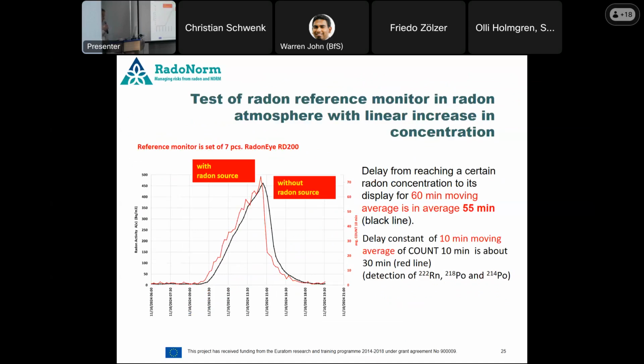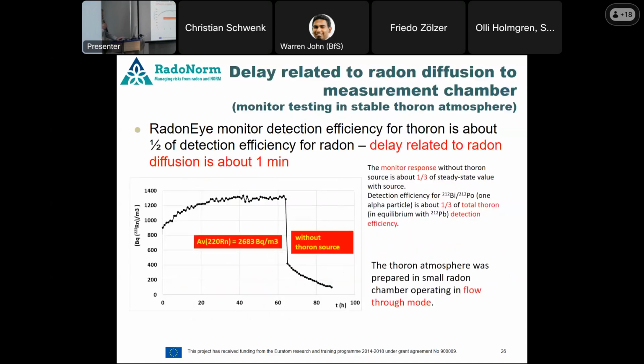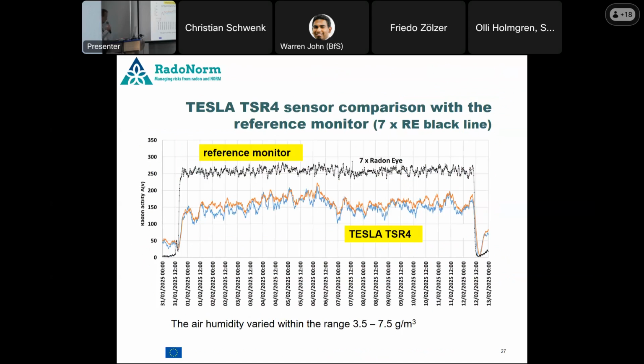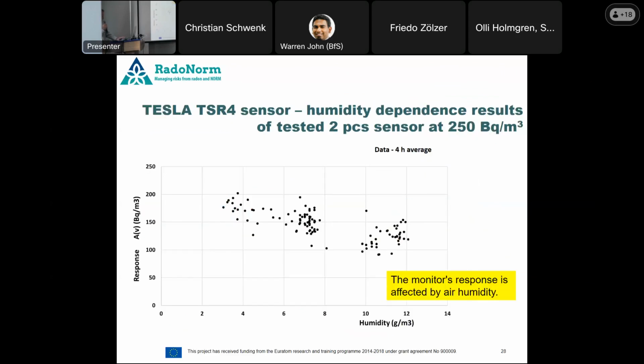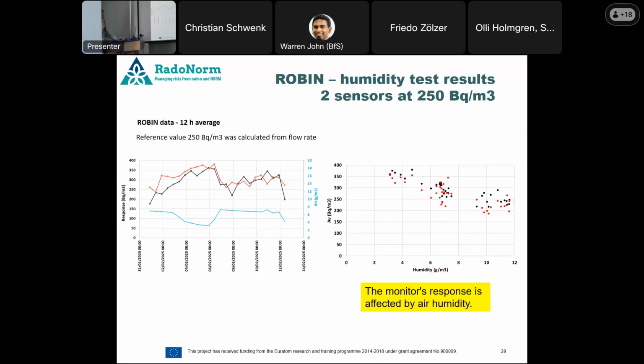We also tested the Radon Eye monitor in a thoron atmosphere. We found that the Radon Eye detection efficiency for thoron is about one half of the detection efficiency for radon. This implies that the delay related to radon diffusion into the chamber is about 1 minute. The next 3 slides relate to humidity test results. For the Tesla and Robin sensors, both responses were affected by humidity. This phenomenon is typical for sensors with the same detection method as Tesla.